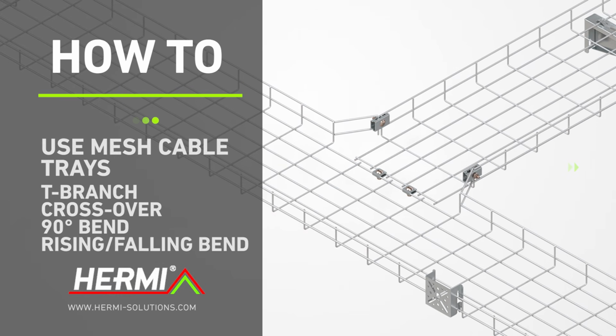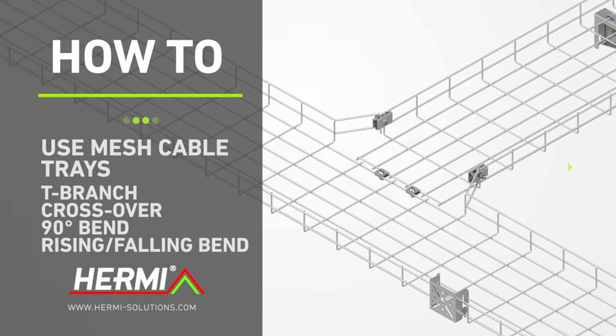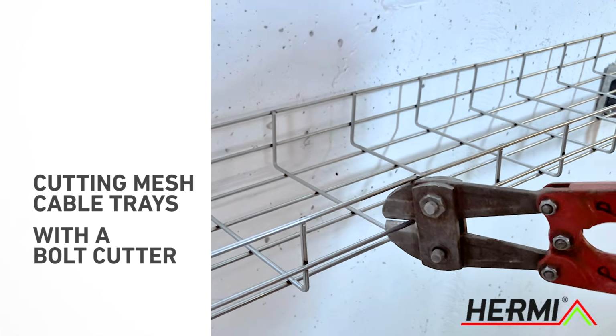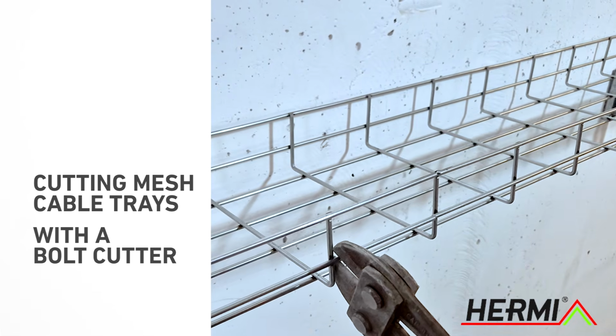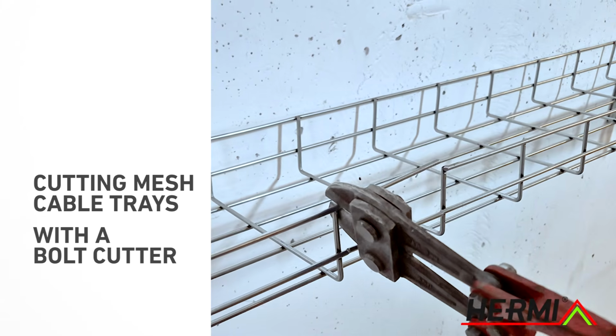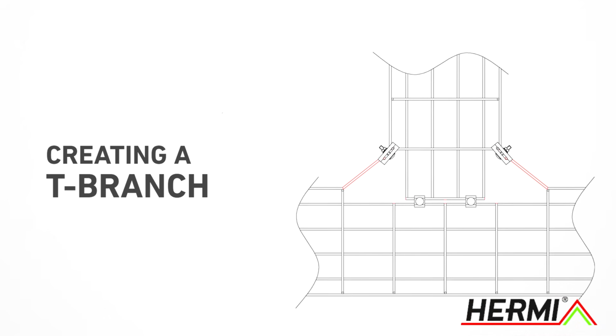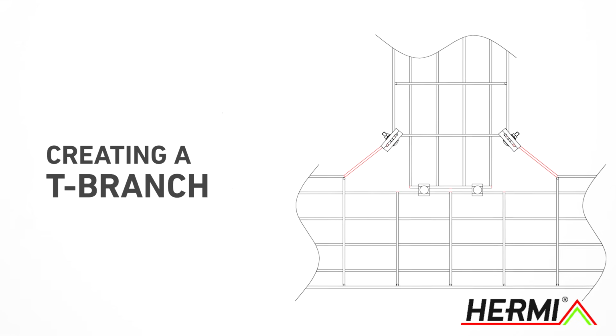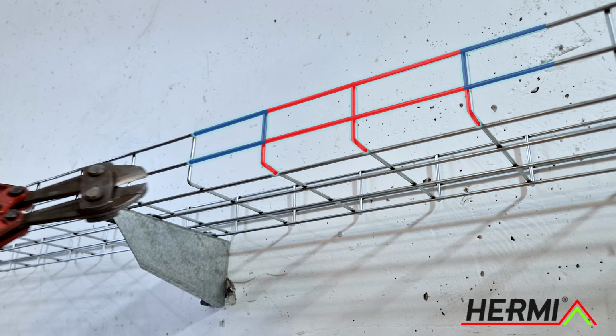In this video, we'll show you how to create T-branches, crossovers, and bends with mesh cable trays. Cut mesh cable trays with a bolt cutter to shorten trays or remove segments. To create a T-branch, mesh cable trays are cut, bent, and joined together with clamps.